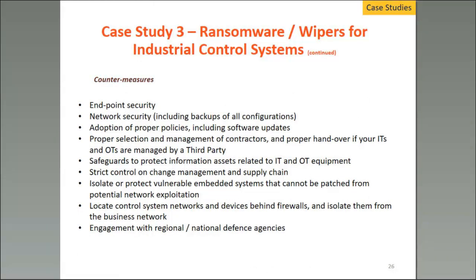What are the countermeasures? First, endpoint security is one good suggestion. Second, network security, including backups of all configurations that you have on your own network. The adoption of proper policies for software updates is a very good protection. In addition, proper selection and management of contractors — try to have safeguards to protect information related to your IT and OT equipment, as sometimes this is not done at all. Tight control on change management and supply chain is another big point, and this will most probably be in most legislation in the future. Isolate and protect vulnerable embedded systems which cannot be patched from potential network exploitation. And finally, engagement with regional and national defense agencies may be an additional point.